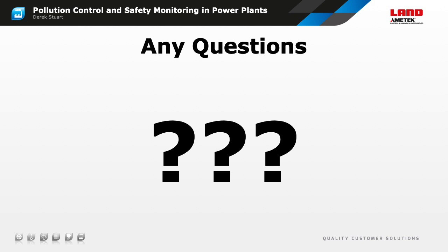Okay, thanks again. Moving on to the next question here. Is air purge really needed if an opacity monitor is operating on a negative pressure process? Yeah, that's a question I get quite often from our customers, and it is tempting to save money by omitting the air purge system and just rely on the draft within the stack to draw ambient air through the purge system and keep the optics clean. I've seen it done a few times, and it sort of works. My concern is always that there's going to be some contamination, so you're going to wind up having to do more frequent maintenance, clean your optics, and so on. And the bigger danger is that there will be some fluctuations of pressure within the stack, and that these will actually expose the sensitive optical components to hot and corrosive stack gases. And when that happens, you get damage occurring really quite quickly.